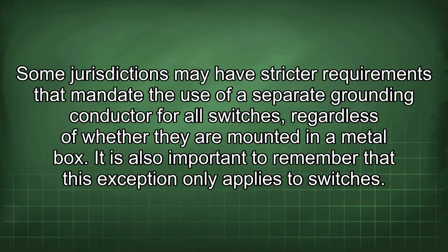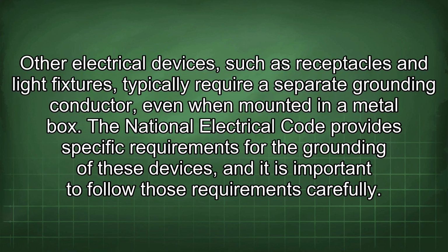Some jurisdictions may have stricter requirements that mandate the use of a separate grounding conductor for all switches, regardless of whether they are mounted in a metal box. It is also important to remember that this exception only applies to switches. Other electrical devices, such as receptacles and light fixtures, typically require a separate grounding conductor, even when mounted in a metal box.